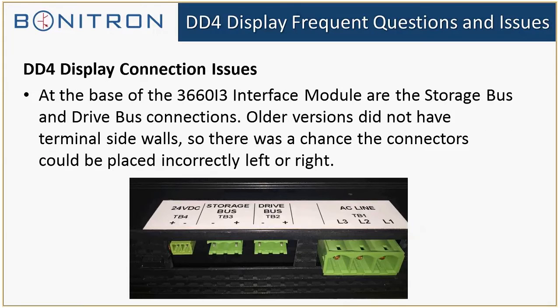At the bottom of our older units, we've since fixed this issue, but when customers are plugging in the connectors at the bottom, you can see how these do not have any sidewalls to these terminals here and here. So what we found is that more often than not, customers would think they were connected straight on with it, but they would actually be off, either left or right, and we would get chaotic information. Either you'd have a storage bus fault, or wouldn't be able to see any storage bus at all, or wouldn't be able to see any drive bus on the display, and that would cause issues. We've since fixed this by simply adding sidewalls and plastic blocking right here. But if there's an earlier display still out there in the world, this could still potentially be an issue.